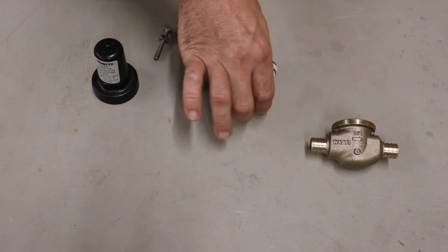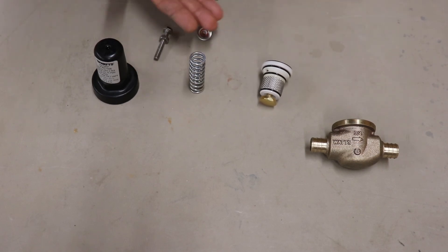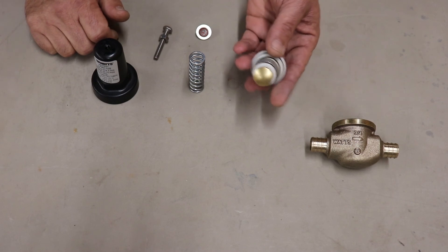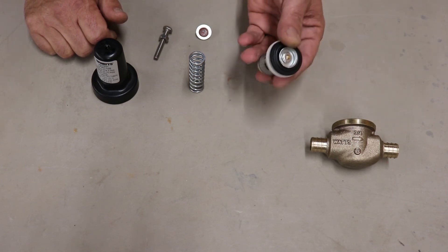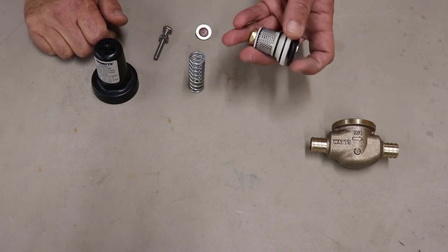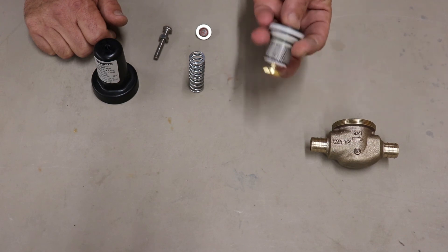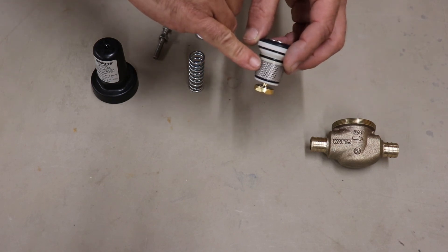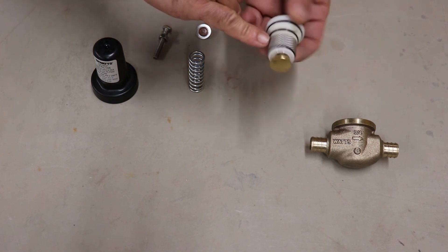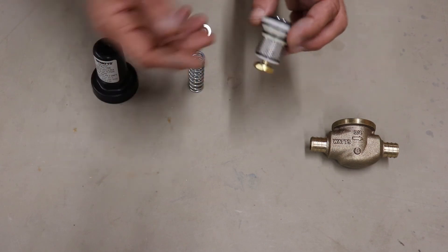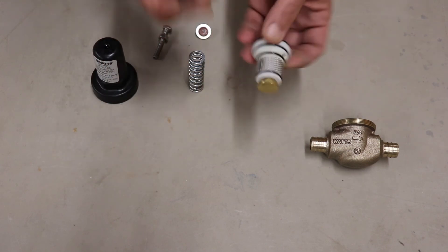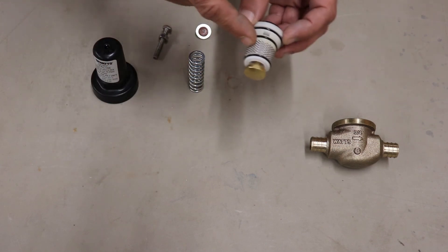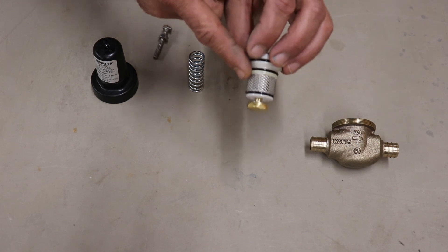The next part here, a lot of things come as a cartridge nowadays so it makes it easier to replace. Now there's a couple pieces in here but you're pretty much not going to take it apart any farther than this. It's got a screen, a filter screen here. Now this is something that can get clogged with sand and dirt and debris either at construction or over time, so if you're having a problem with low pressure you might want to check this screen to make sure it's not full of gunk.